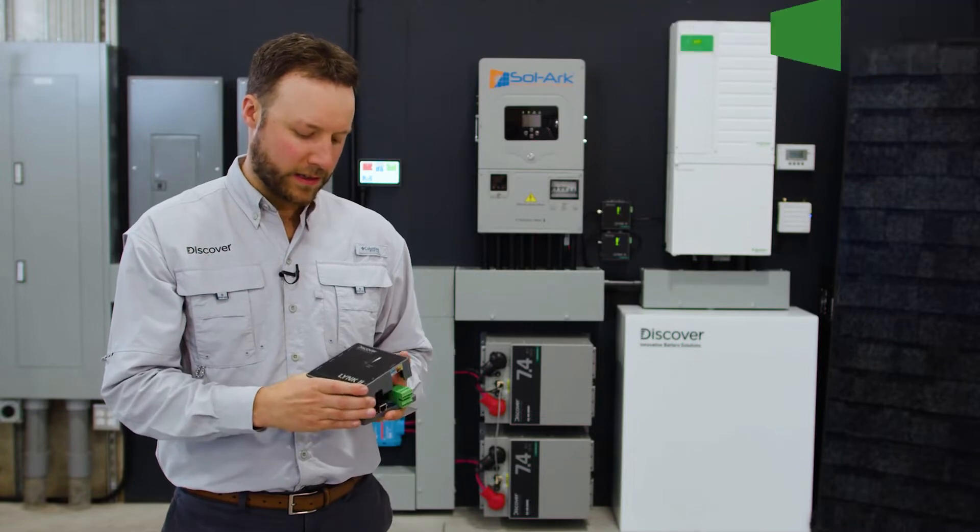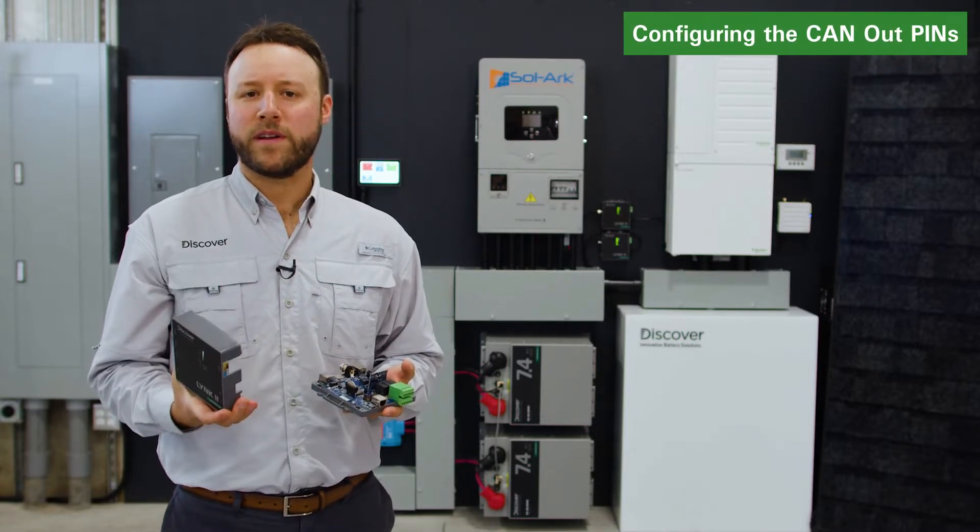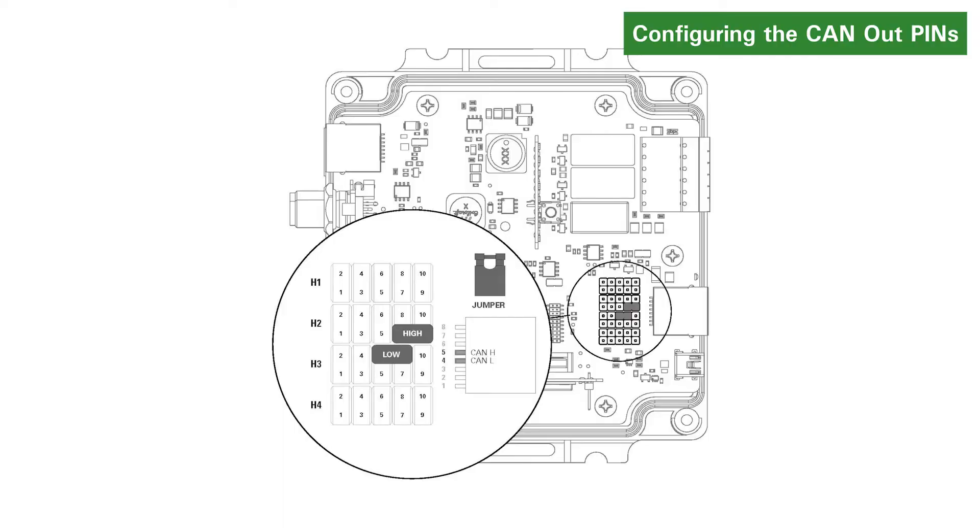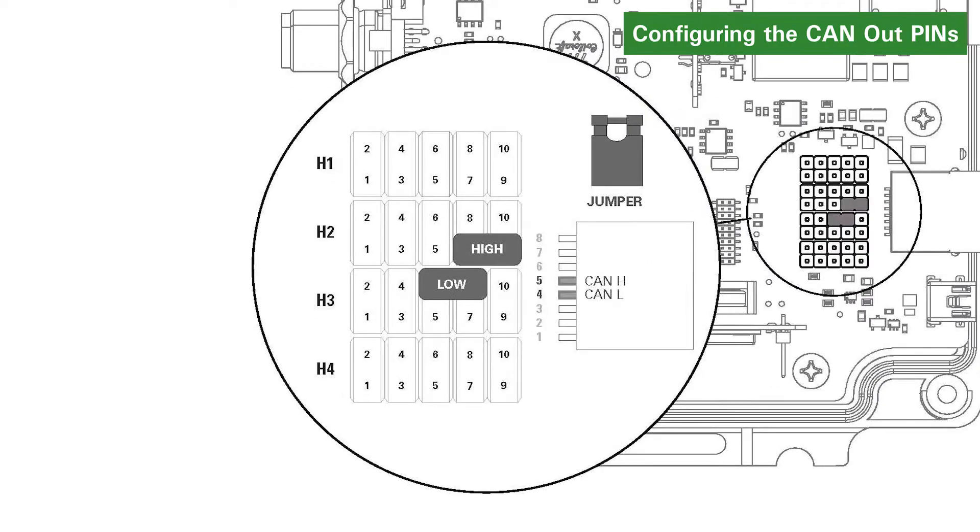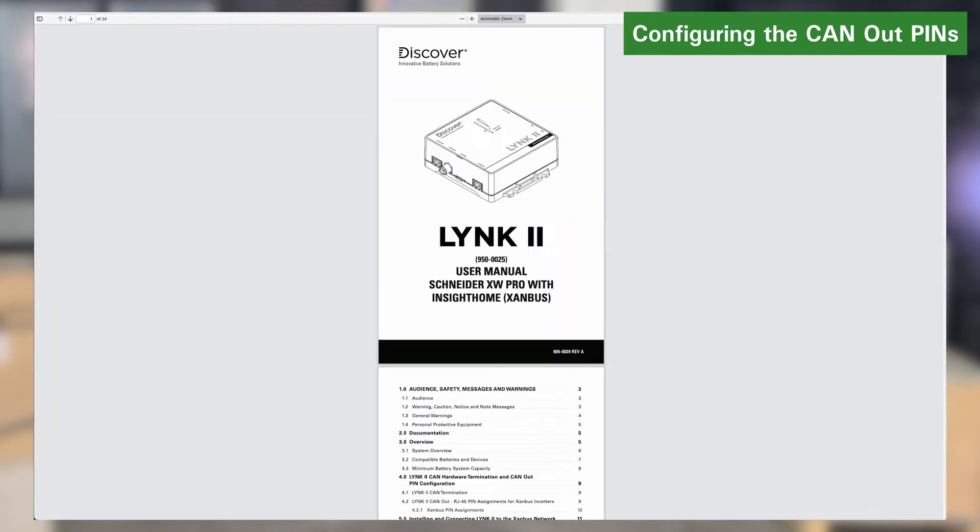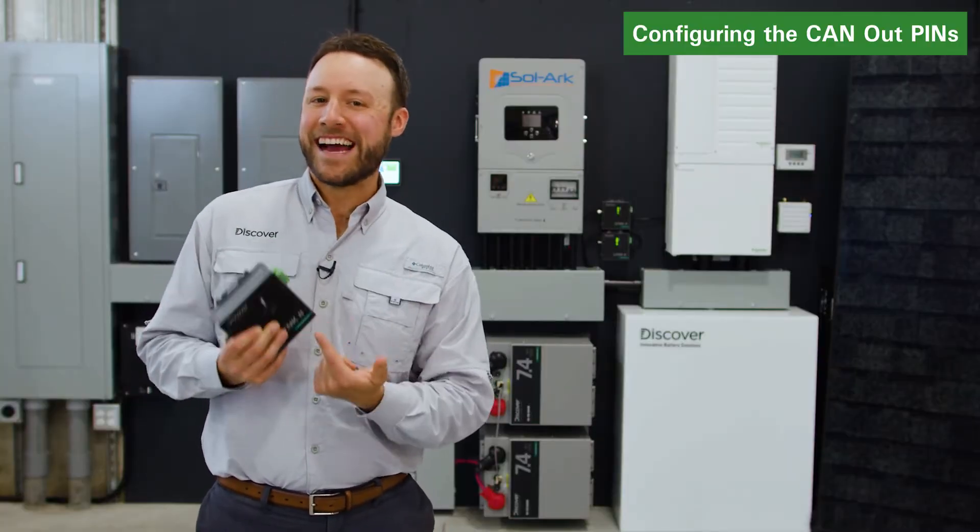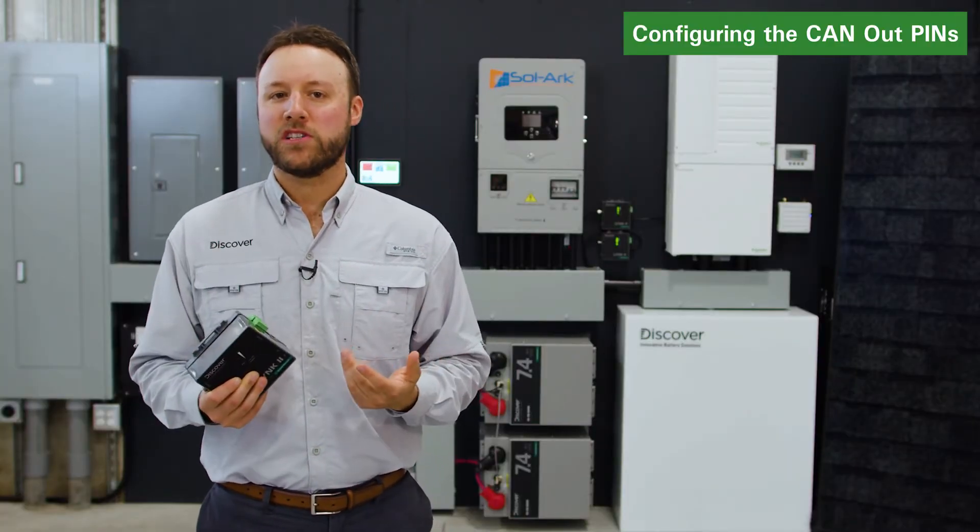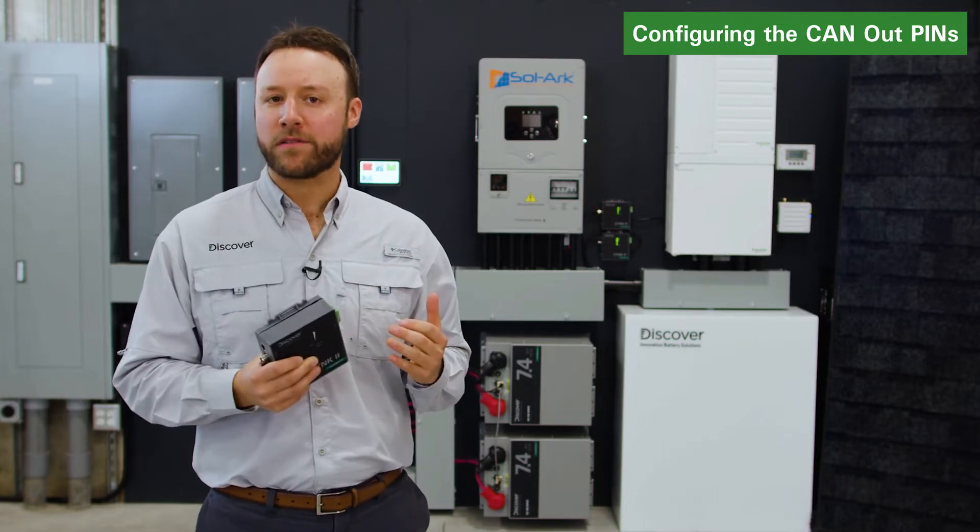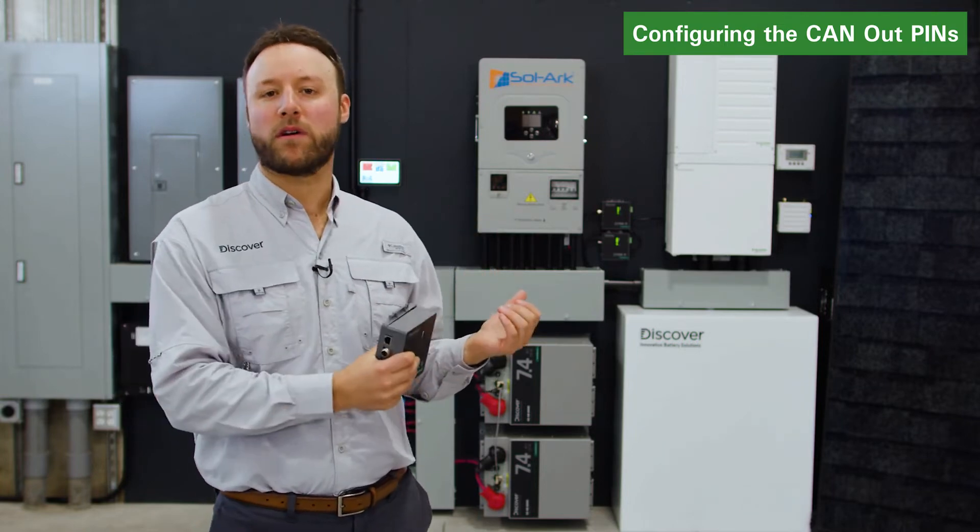Before starting the installation, you must configure the CAN-out pins of the LINK2 gateway to match the CAN-low, CAN-high pins for the Schneider XW Pro inverter charger. Download and consult the LINK2 user manual, Schneider XW Pro with Insight-Home Xanbus from the discoverbattery.com website to learn how to position the internal jumpers that configure the LINK2 CAN-out pins. We've already configured the jumpers inside the LINK2 for the Xanbus, so we can now connect the LINK2 to the Discover batteries and the Xanbus network.